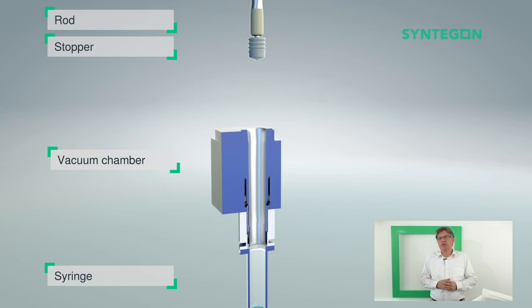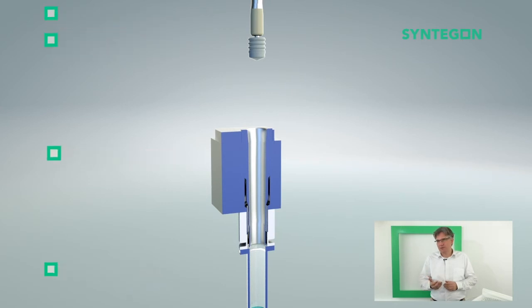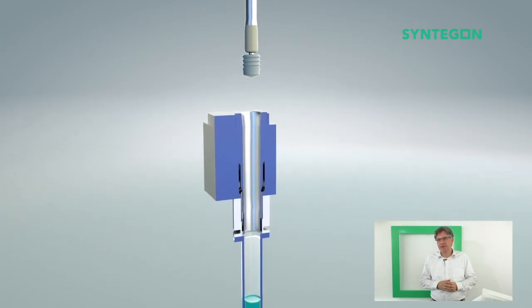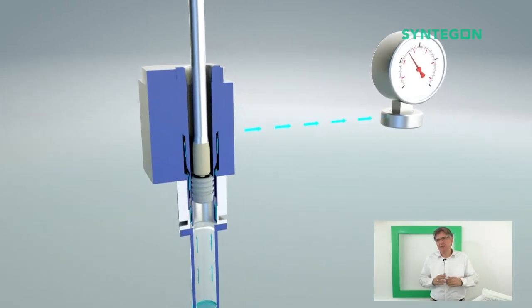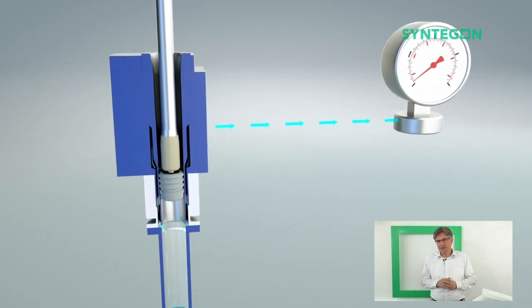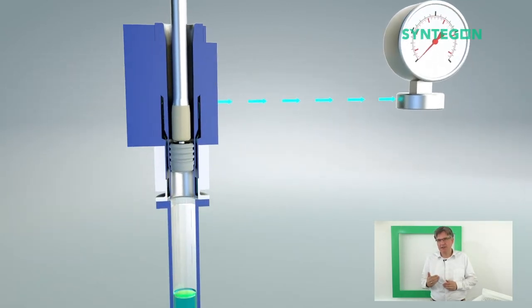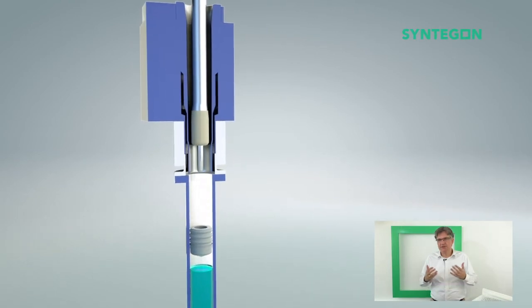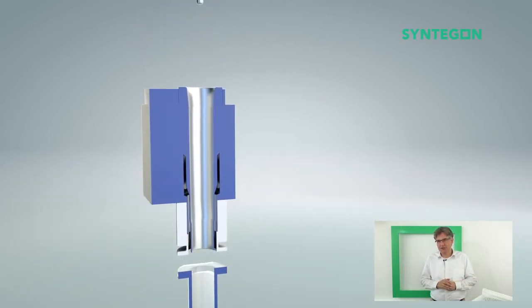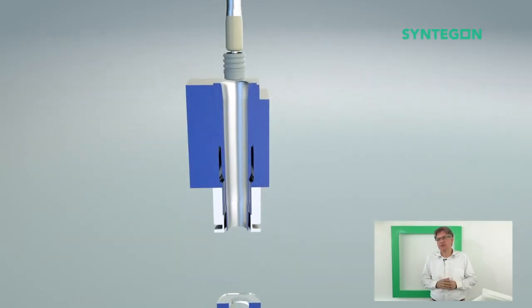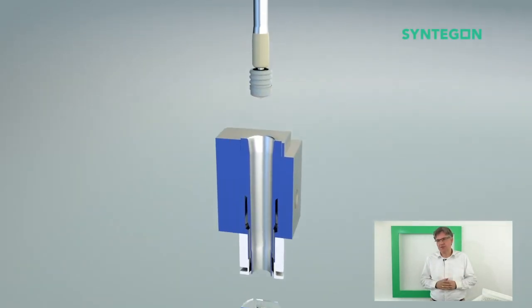And now I will explain to you how the process works. The stopper is pushed by the rod into the vacuum chamber. Then the vacuum is applied between the stopper and the fill level. As soon as the right vacuum pressure is reached, the rod pushes the stopper into the syringe.